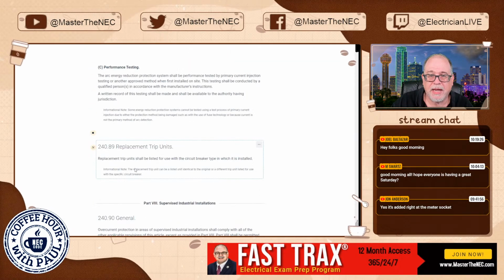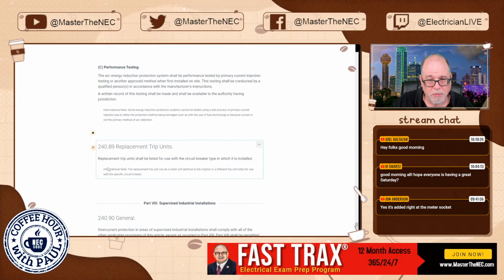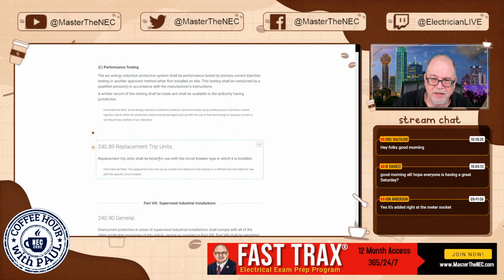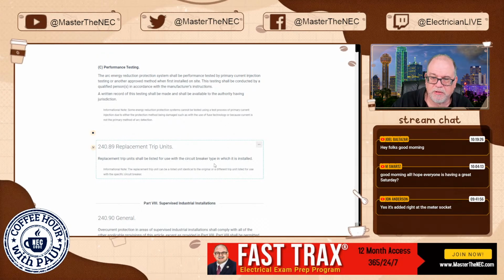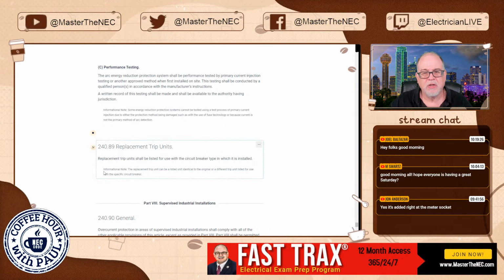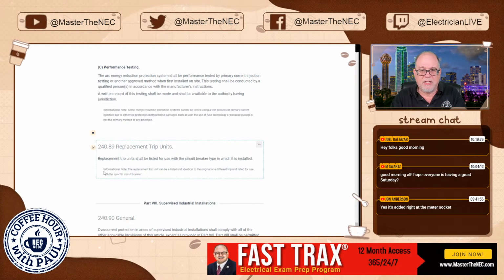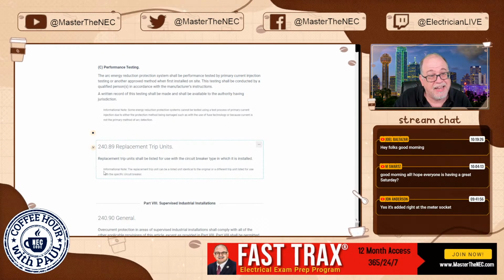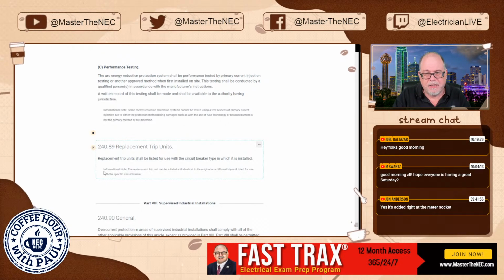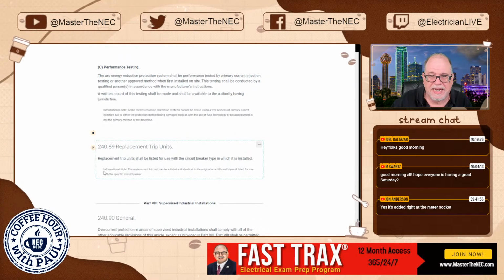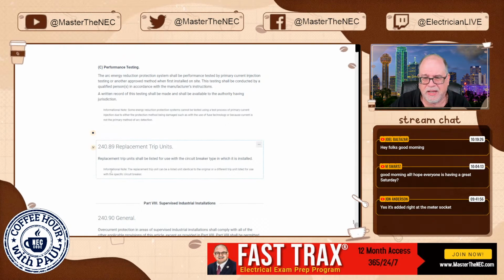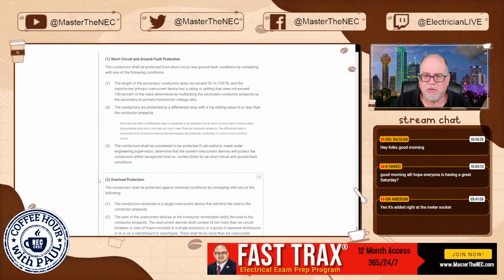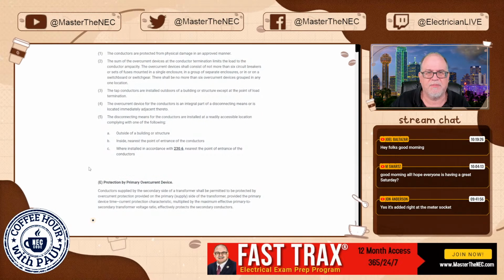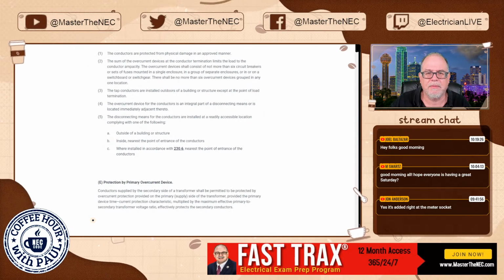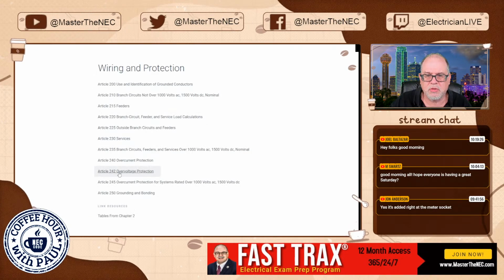Let's see here. Okay, replacement trip units. Replacement trip units shall be listed for use with the circuit breaker type in which it is installed. So if you're going to take the trip unit out of a circuit breaker that accepts these trip units, then make sure that whatever you install back in it has to be listed. It should go without saying. And then everything else, there are not any significant changes there we want to look at. Okay. All right, we're going to now go to 242.